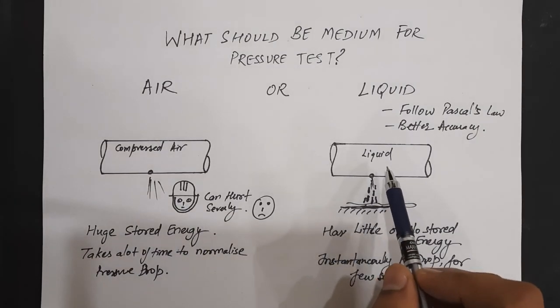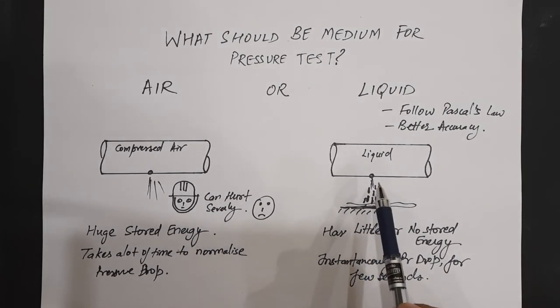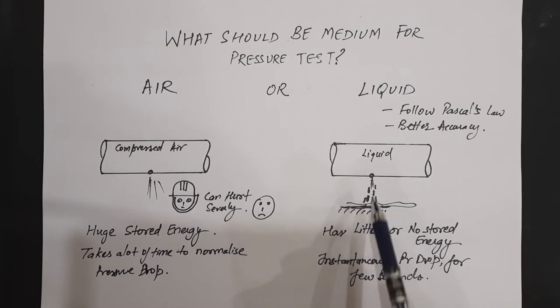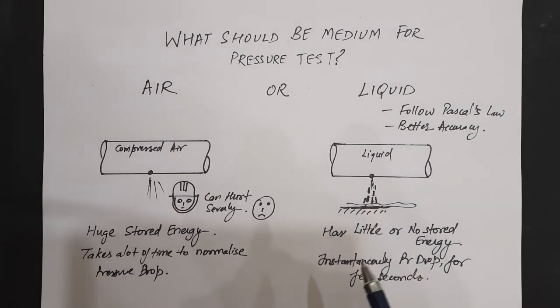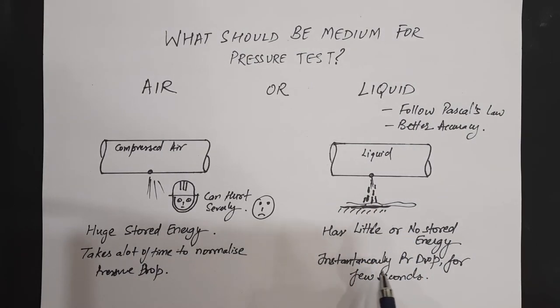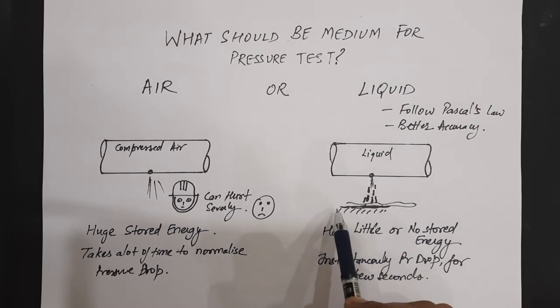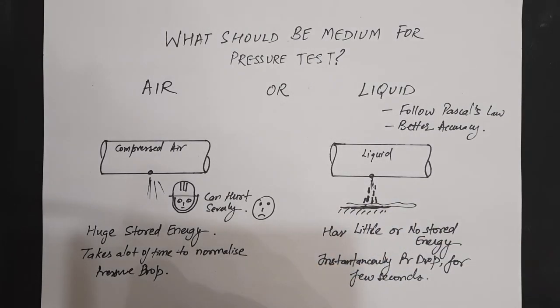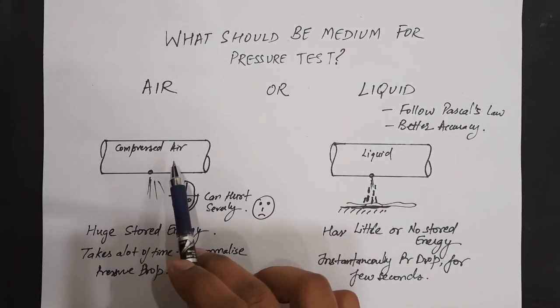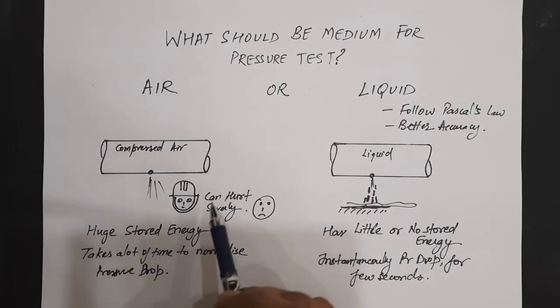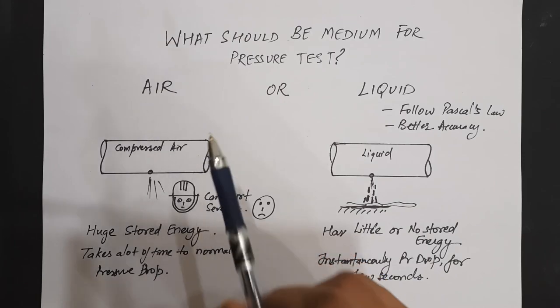While, in case there is rupture in the manifold for the liquid, then of course it will release the pressure instantaneously. But it will not be so much disastrous as compared to the compressed air. Hence, the instantaneously pressure drop will be there for few seconds. But it will be reducing its pressure. Whereas, the compressed air will keep on reducing and it can hurt any personnel. So this is the main reason for taking the liquid to be the medium to conduct pressure test.